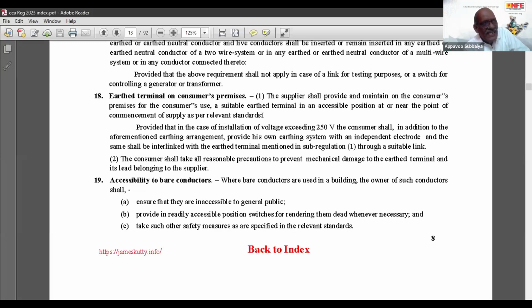So this is the thing we are missing. Either the consumer is reluctant to provide his protective earth terminal at the supplier's earth neutral, as we call it. A suitable earth terminal in an accessible position near the point of commencement of supply. So the simple thing is, the consumer has to connect it, and he has to provide one more earth also at the point of supply. And that is mandatory only in case he is a three phase consumer above 250 volt.